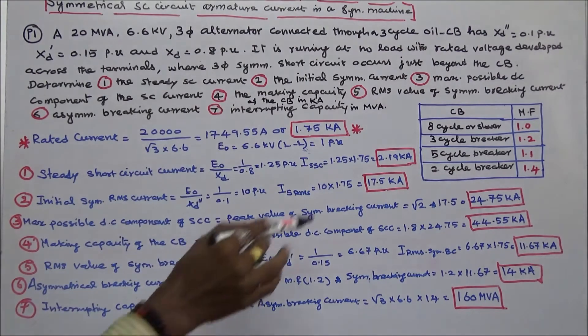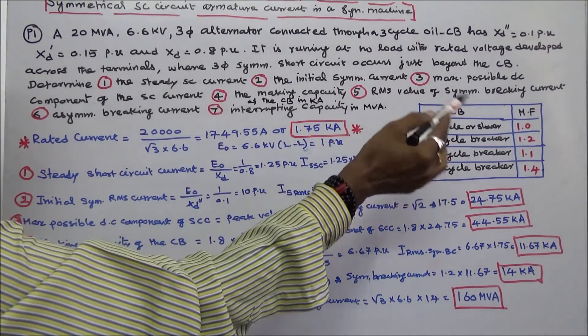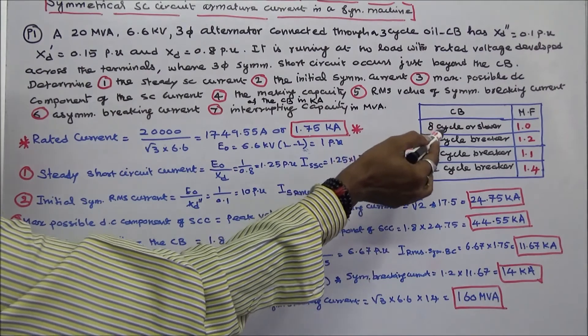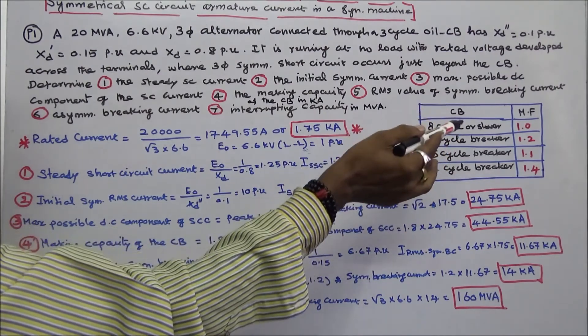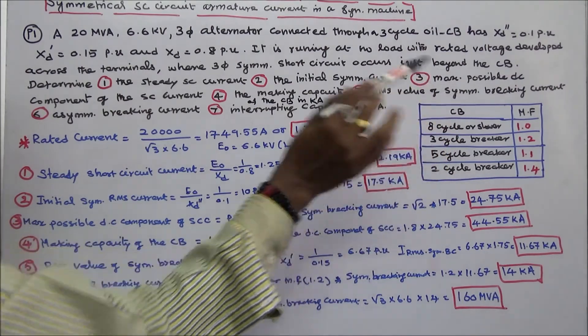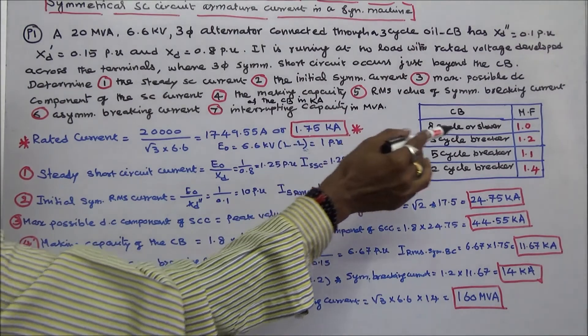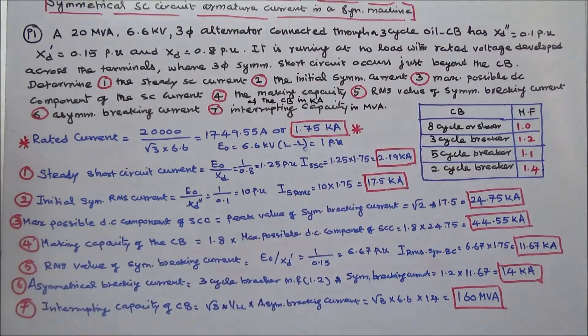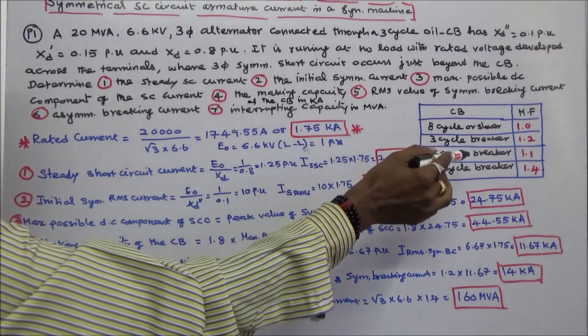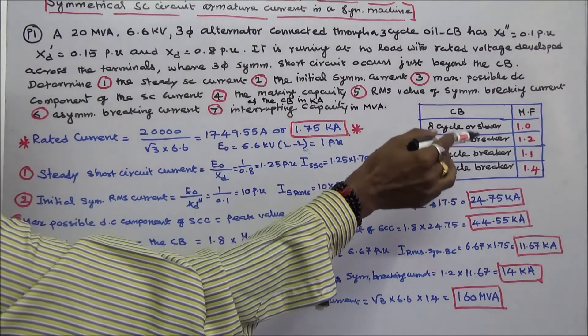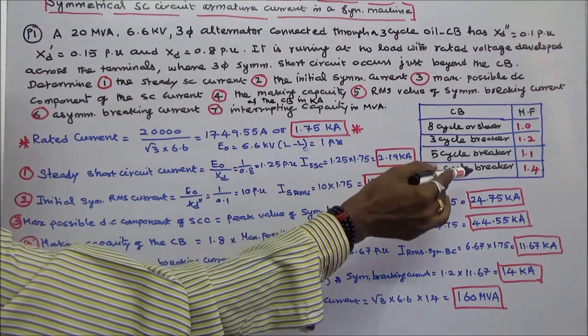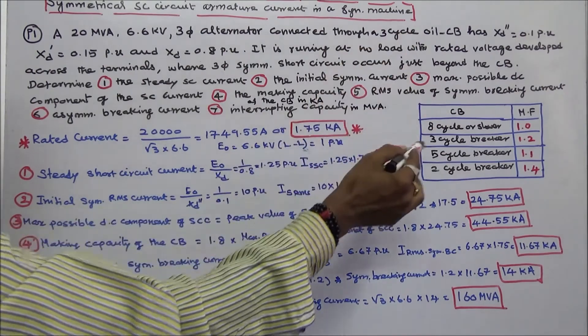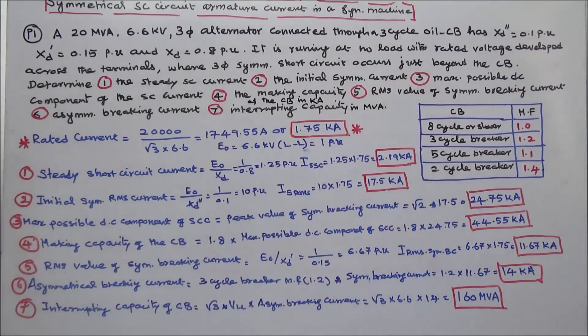The multiplication factor for the circuit breaker: 8-cycle or slower breaker, multiplication factor is 1.0; 3-cycle breaker, multiplication factor is 1.2; 5-cycle breaker, multiplication factor is 1.1; 2-cycle breaker, multiplication factor is 1.4. Here, the given breaker is 3-cycle, so we take the multiplication factor of 1.2.